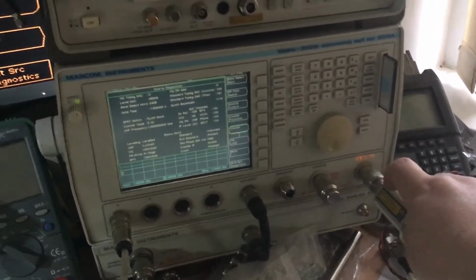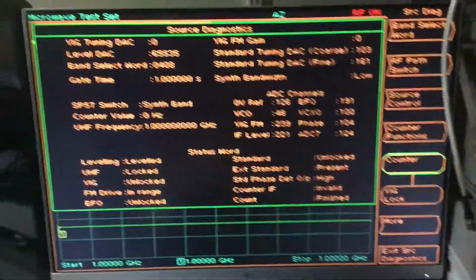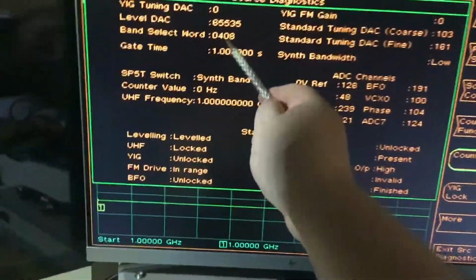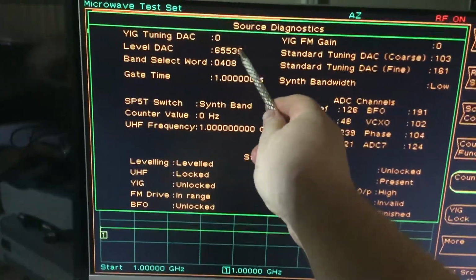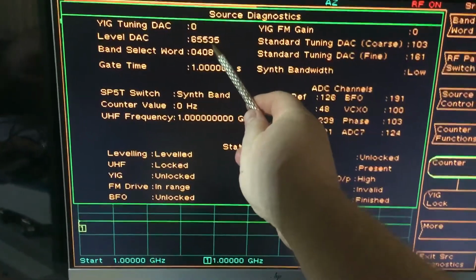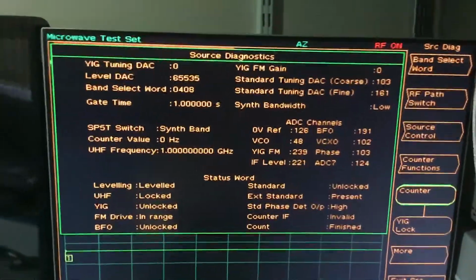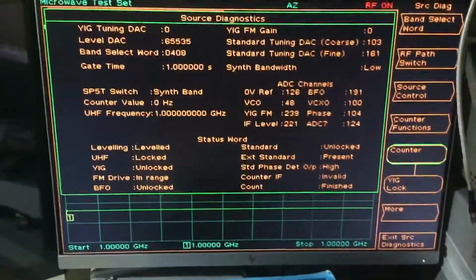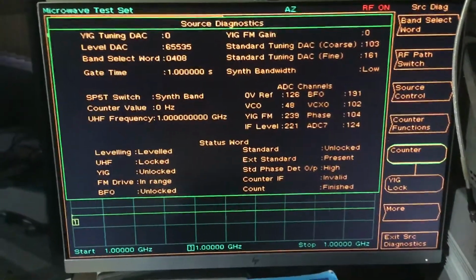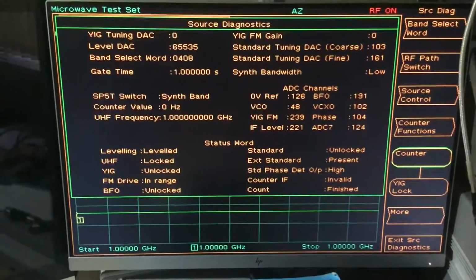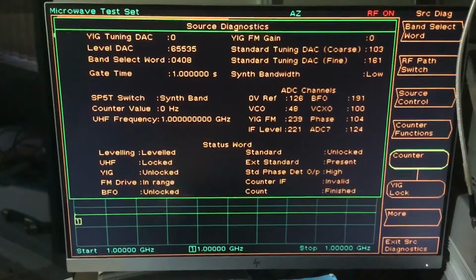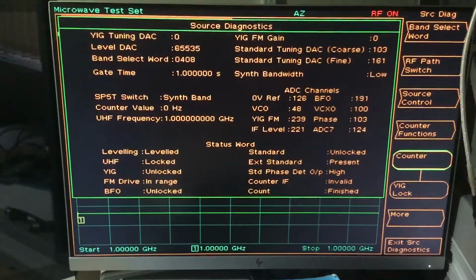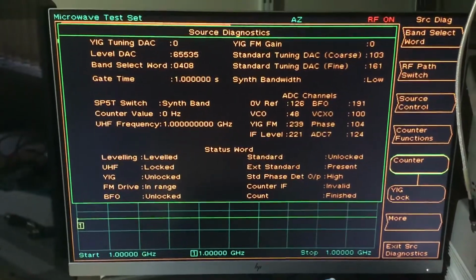The test set outputs an RF level which is decreed by the DAC, which is just here in the top left hand side of the screen, this 65,535 value. Basically that value goes from 0 up to 65,535, whatever it is. That's its entire range, and each instrument has a different value depending on its own individual characteristics.